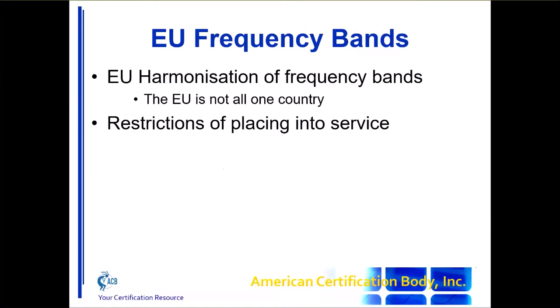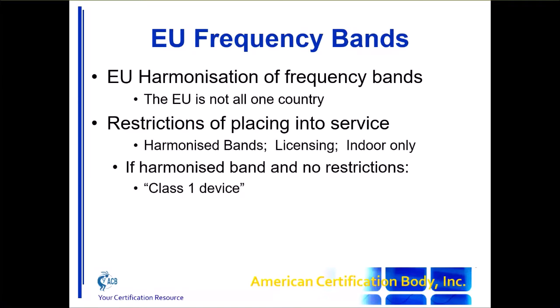What it can mean is that you've got a harmonized trade route under the CE marking directive, but you may not have harmonized frequency bands. The frequency allocations in each country may not be the same, and this can lead to restrictions on placing the radios into service. It could be okay to put the radios into the market in Europe, but that doesn't mean they can be used in every country. So if the frequency band can't be used the same in every EU member state, it's known as a non-harmonized frequency band. If it can be used in every state, it's called a harmonized band.